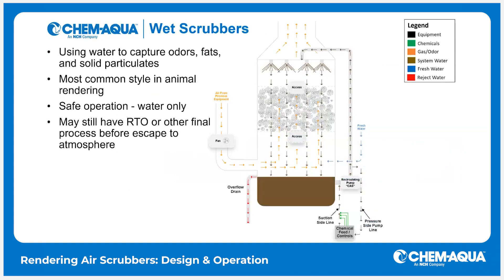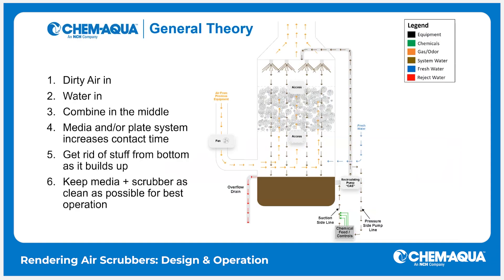We're going to specifically talk about wet air scrubbers in this training today because that's the most commonly used one in rendering. Wet scrubbers use water to capture the fats, solids, and odors in the rendering process. They are very safe to operate because they generally just use water, though some may still have a flame-based RTO style as a final polish on the way out to atmosphere.